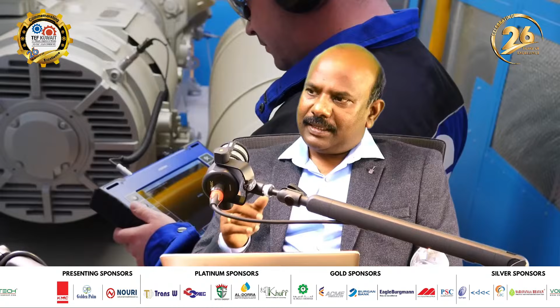For example, if equipment is running with 2 mm per second or 25 microns vibration, that is a standard baseline value. So the data are being collected on a real-time basis, 24 by 7. Whenever the values are within these 25 microns, there will be no issues. When the data starts going up and down, there is a fluctuation, or there is a gradual increasing trend, or there is an instant high value, then it will be analyzed. So whenever the values are detected in an increasing trend or abnormalities are observed, then analysis has to be performed.